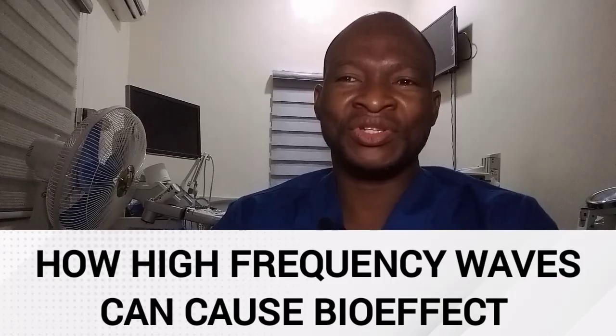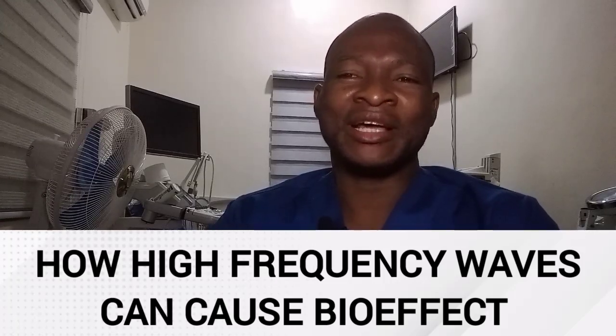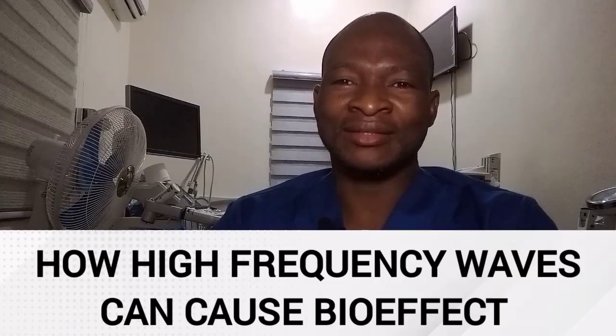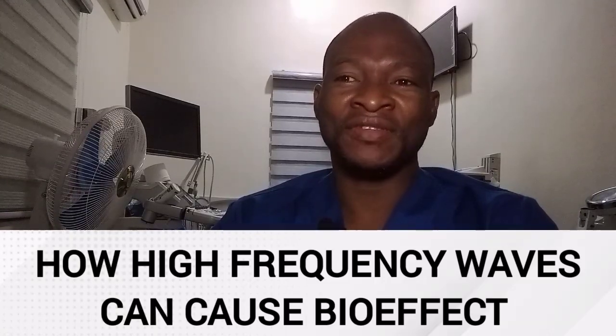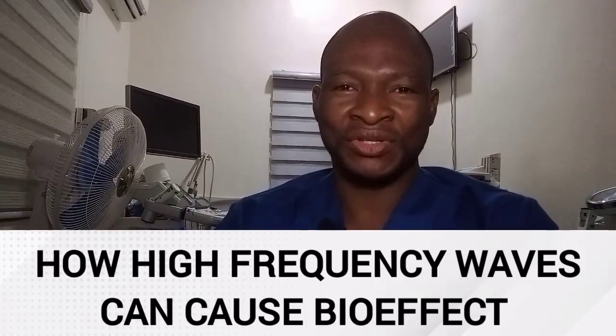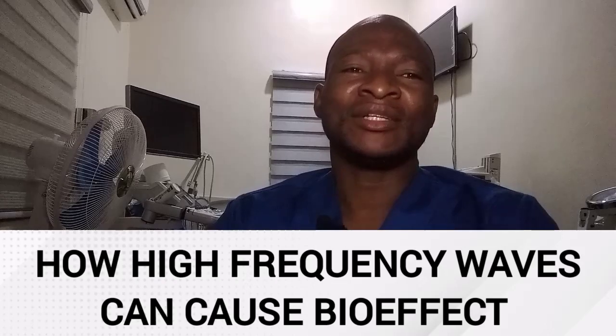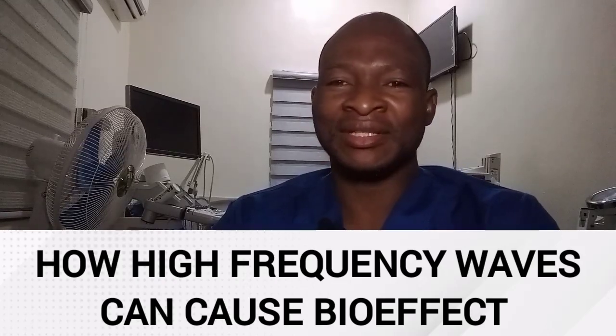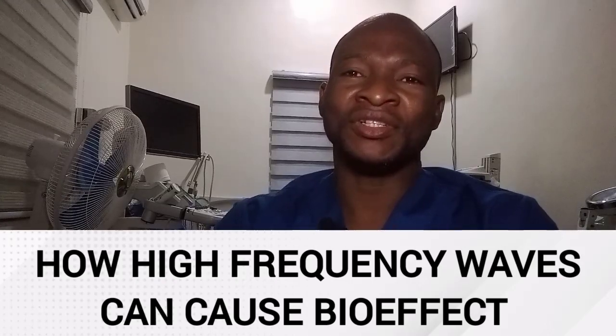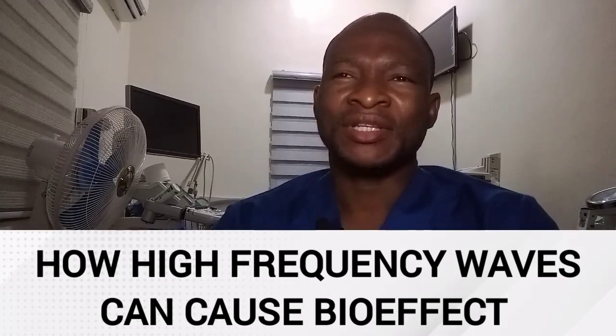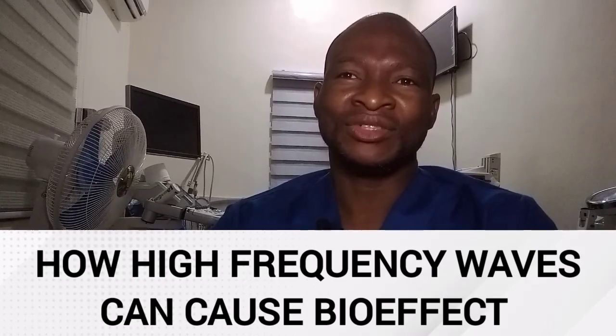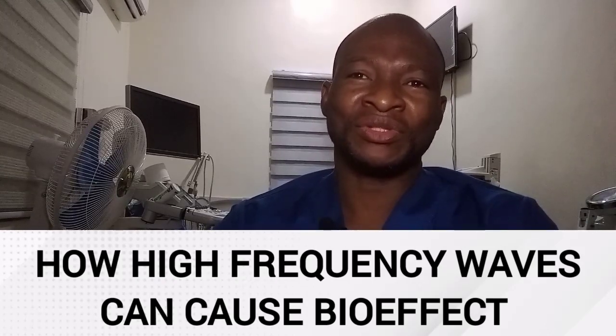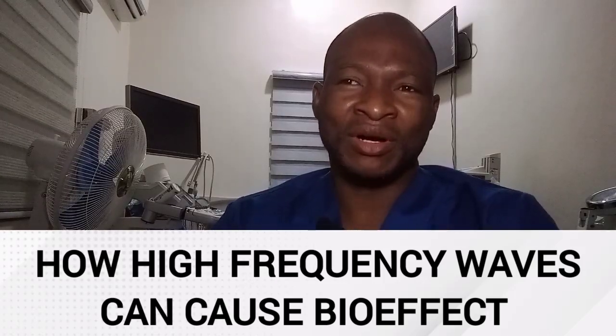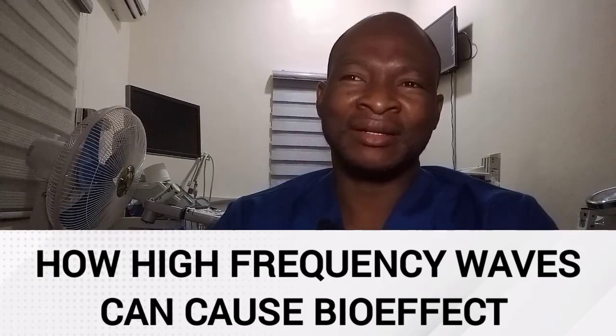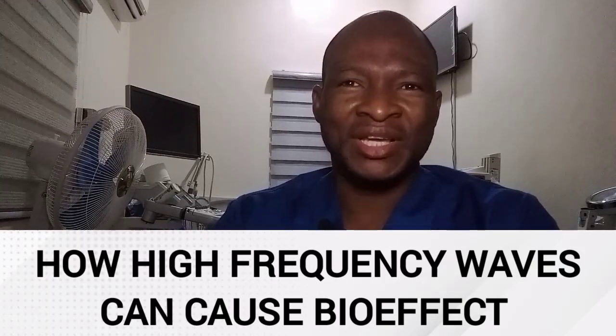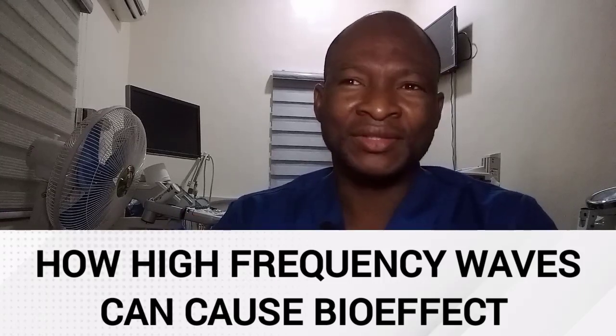Now, the strength with which the particles of a medium vibrate is determined by the amplitude of the wave and will depend on the power and intensity of the ultrasound beam, in other words, the ultrasonic field. The rate at which the particles vibrate is determined primarily by the frequency of the transducer.